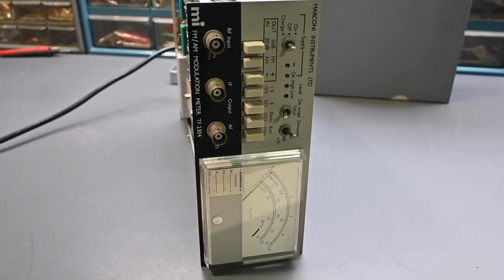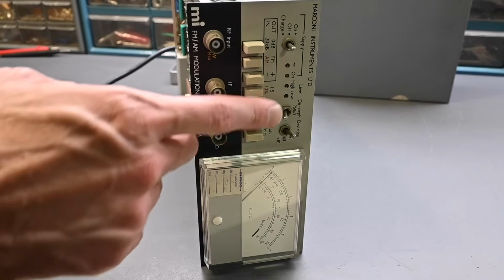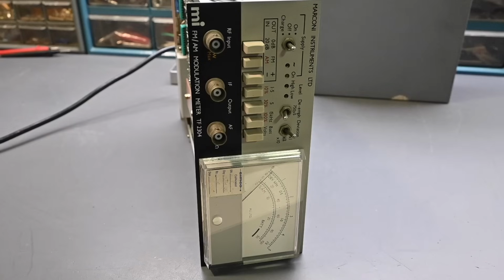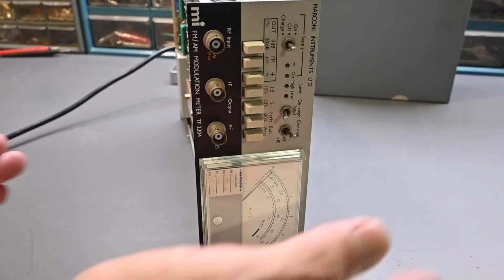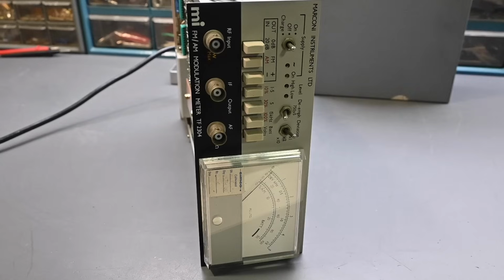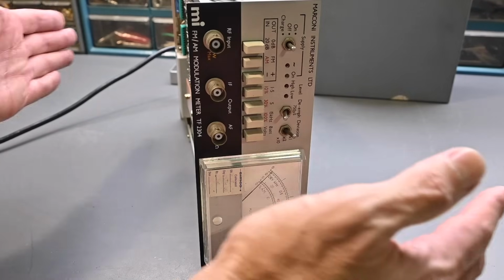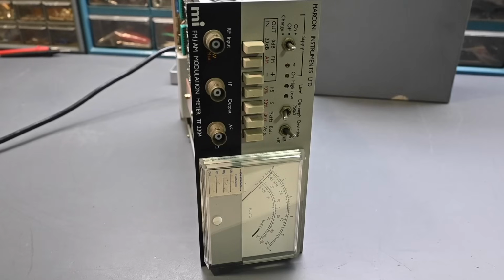All right, let's set the calibration on the middle range, and I'll double check the calibration on the high range as well. And there is no adjustment for the lowest range. Now I folded that RF assembly back down into position. I thought that would be a good idea because it might act like somewhat of a shield over this lower circuit board, and I didn't want to make the calibration and then fold that down and have it change the adjustments or the settings.